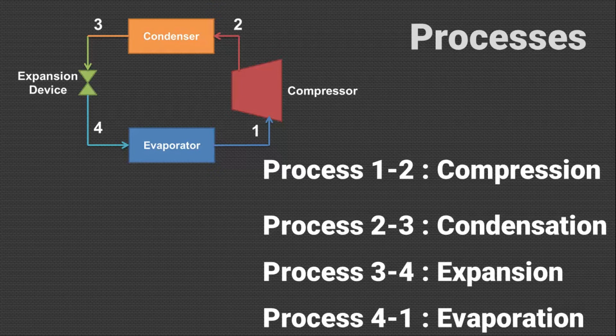By losing heat to the cooling media, the refrigerant gets condensed in the condenser. This liquid refrigerant is then throttled through the expansion valve, which is the process of expansion shown from 3 to 4. The refrigerant is throttled to low pressure in the evaporator. At such low pressure, this liquid refrigerant starts to evaporate, absorbing latent heat of evaporation from the surrounding space which is to be cooled. By absorbing heat from the space, the refrigerant evaporates and converts into vapor form. These vapors are then again passed to the compressor and in this way the cycle completes.